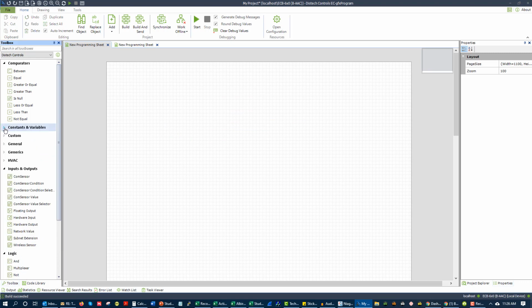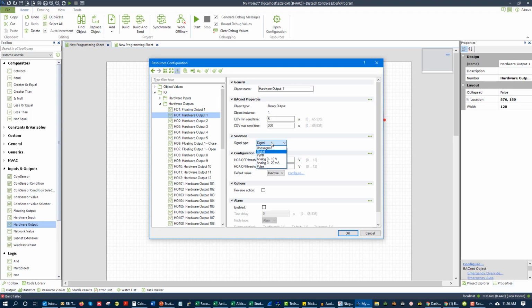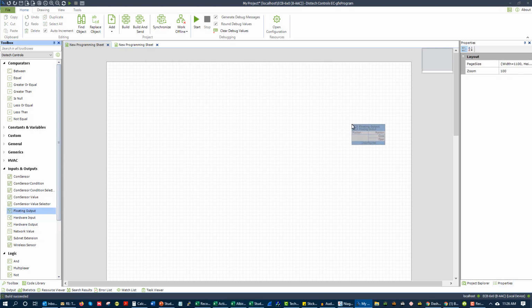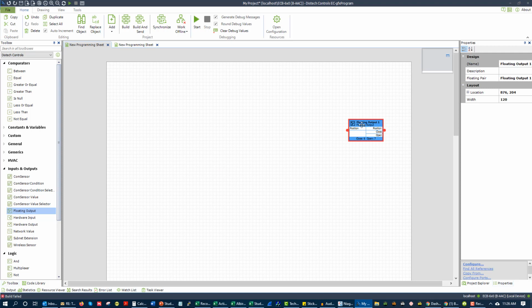Now let's look at floating control. So floating control is another thing. Let's go here. And oh yeah, that's right, it's not here in the software. So with floating control, and you'll see this a lot with VAV boxes where people don't want to spend money on proportional valve actuators for their reheat, they use this floating control because it's in theory a little cheaper. It's just cheaper to run the extra wire than it is to pay for the actual electronics in an actuator that are required for proportional control.